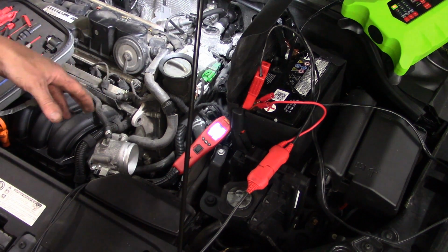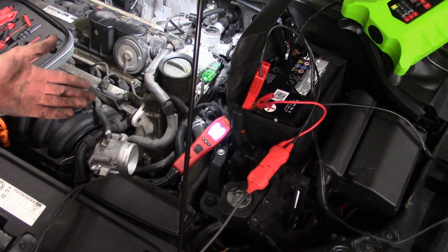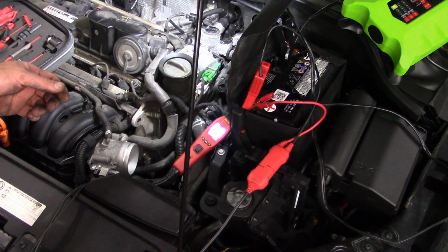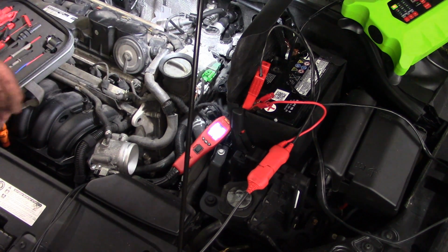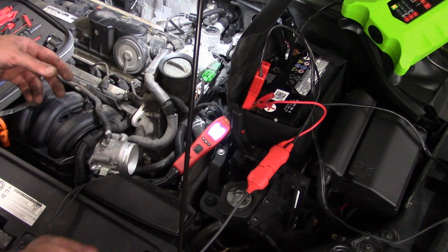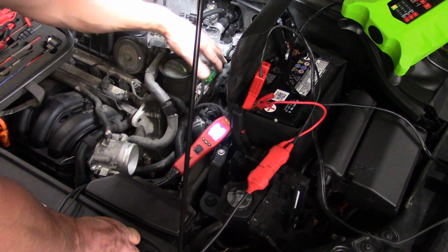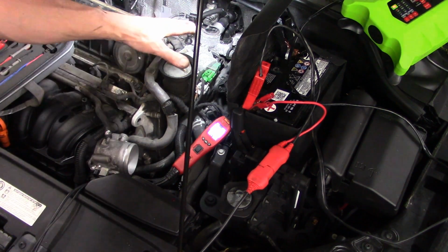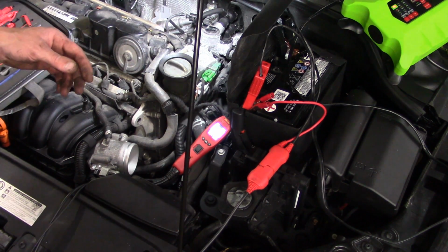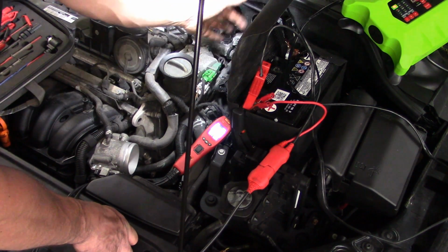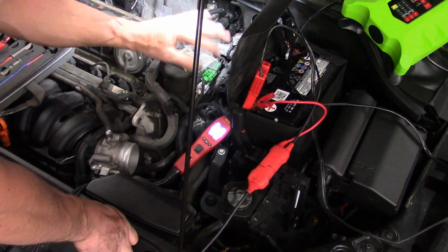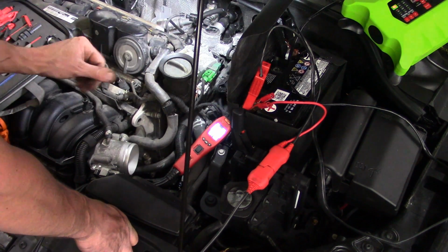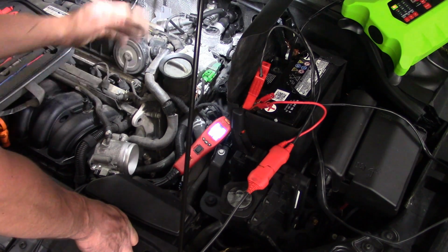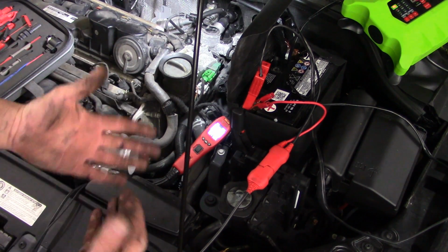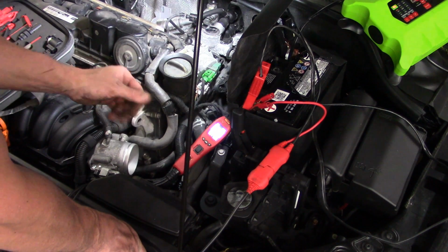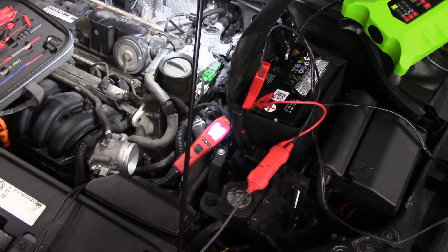I'm going to finish checking the rest of the air system, which just entails turning the pump on, to make sure that valve actually seals, and then make the call - because if this valve leaks and is burning up these sensors, we want to know that too. Can this valve really hold pressure? That's one thing we need to know. Typically if they don't, all this plastic melts almost instantly, so I assume it's sealing, unless there's a backup mechanical check valve in there - we don't know that either. Then we're just going to make the call and order a part.